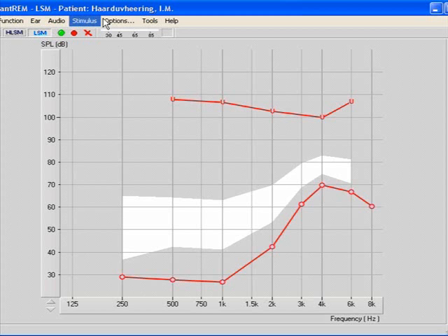The advantage of the adaptive part of this is that even if the background noise moves around the patient, the hearing aids can keep up with that and always keep speech optimally audible. The problem has always been that traditional real ear systems force the practitioner to disable this adaptive system.